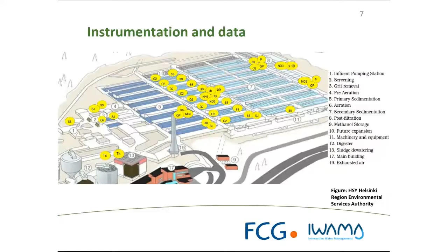Some usual online measurements in wastewater treatment plants are shown here. These are used for different purposes, and some for instance, conductivity is used for monitoring changes in the influent wastewater. Then, of course, dissolved oxygen concentration is used in aeration process and control of it. We have different nutrient concentration analyzers and also sensors which are used for control purposes. Sludge blanket level is something that used to be quite challenging to measure, but the instruments are better nowadays, and this is used especially in a secondary settling tank.